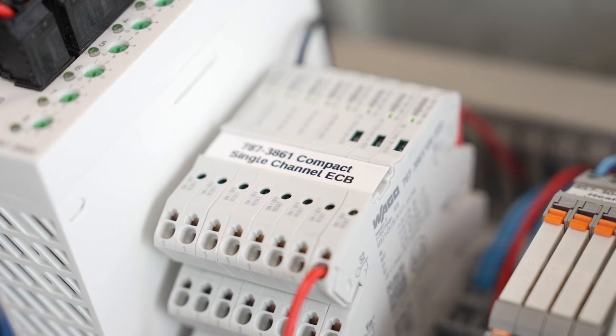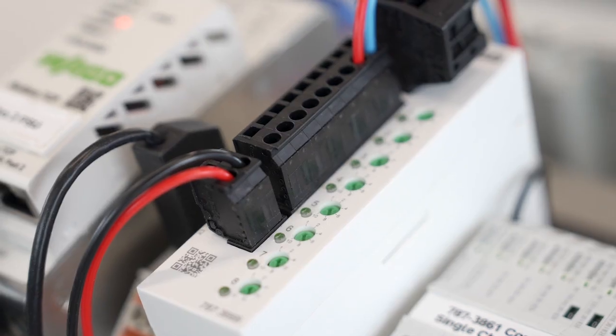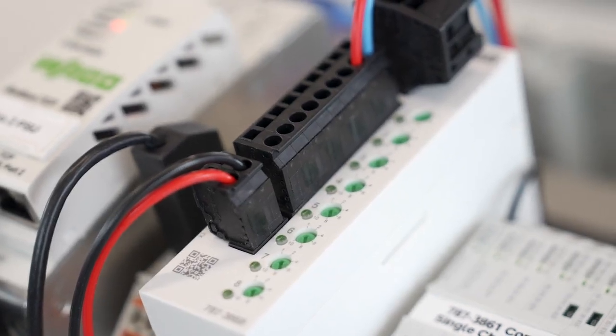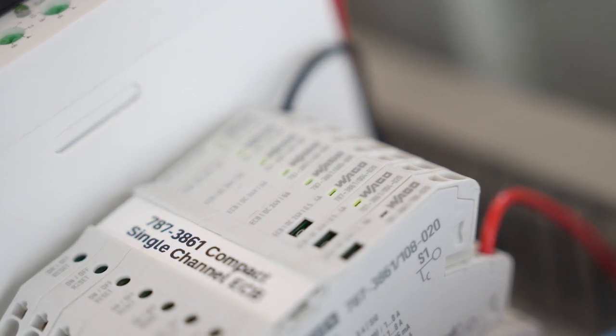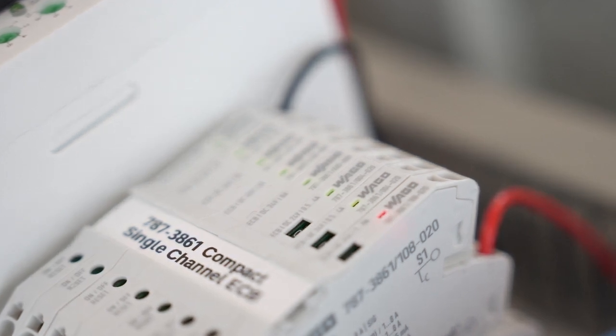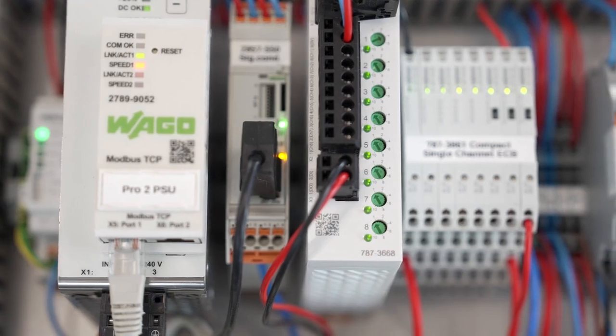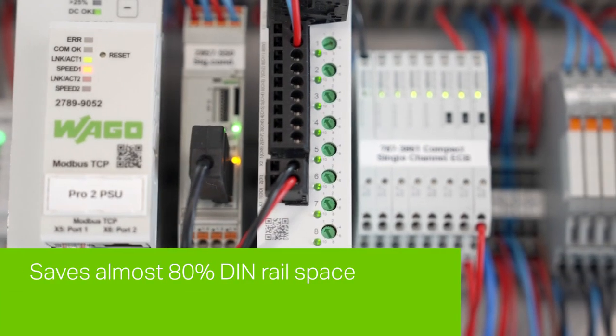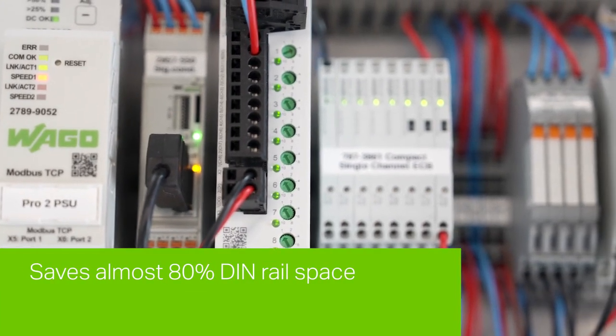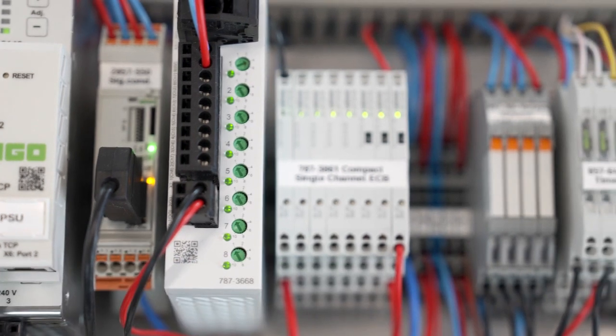WAGO's electronic circuit breakers, or ECBs, are designed to protect your 24-volt DC circuits from overloads and short circuits. Compared to traditional methods such as fuses and MCBs, an ECB offers big benefits. They're extremely compact - the 8-channel saves almost 80% DIN rail space compared to 8 MCBs.